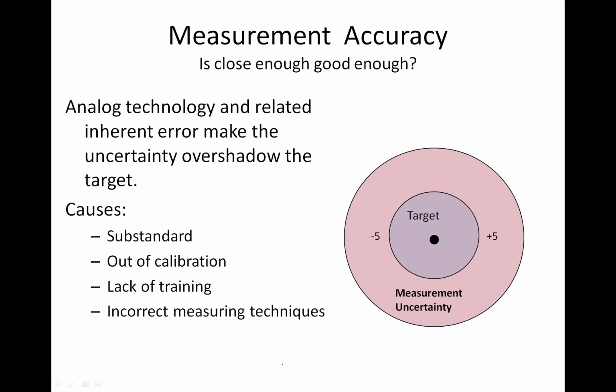And a lot of technicians, including myself, I didn't realize this for years as I was doing this type of work. It causes our substandard instrumentation. You're trying to do a job with the wrong tools. A lot of us buy tools simply because they're cheap, they're inexpensive. We want to find a low-cost solution, and so we use the wrong tool for the job. Out of calibration. When you buy certain types of measurement tools like K-type thermocouples, they're not accurate out of the box. When you take one of those and you plug it into your meter, you have to go through a calibration procedure, and if you're not doing that, you don't know how accurate that K-type thermocouple really is.